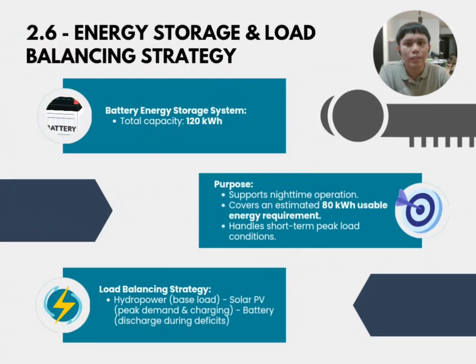Alright, now we are at the next slide, which is 2.6, where we are going to talk about the energy storage and load balancing strategy. So the battery energy storage system has a total capacity of 120 kilowatt hours. The purpose of this energy storage system is to support the nighttime operation. It covers an estimated 80 kilowatt hours of usable energy requirement.